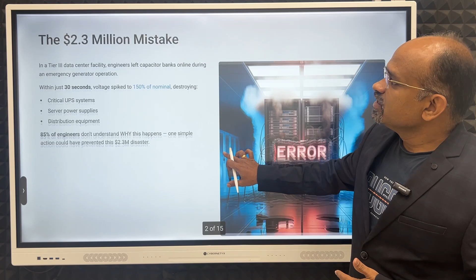See, during the normal scenario, when your electricity board or city power is on and supply is feeding, the capacitor banks should be operating so that they correct the power factor. So the EB board will not charge us a penalty. So the capacitor bank is very important. We need to maintain the power factor. But when the DG kicks in, then you should switch it off.